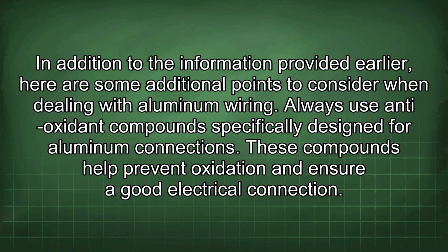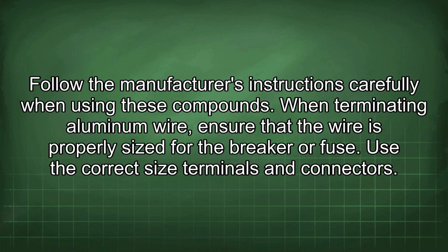In addition to the information provided earlier, here are some additional points to consider when dealing with aluminum wiring. Always use antioxidant compounds specifically designed for aluminum connections. These compounds help prevent oxidation and ensure a good electrical connection. Follow the manufacturer's instructions carefully when using these compounds.